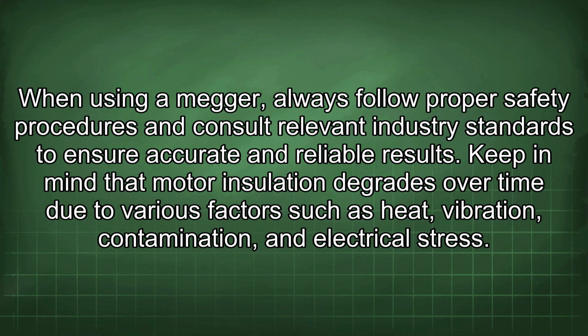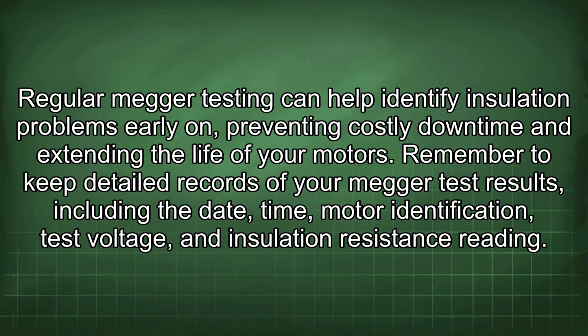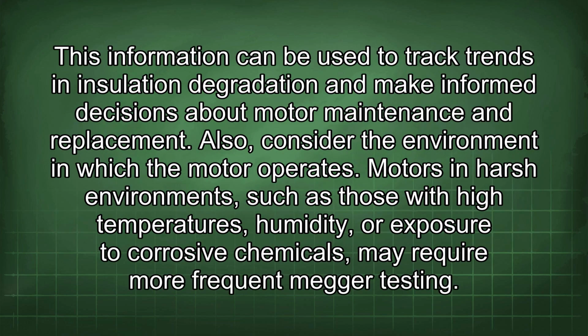Keep in mind that motor insulation degrades over time due to various factors such as heat, vibration, contamination, and electrical stress. Regular Megger testing can help identify insulation problems early on, preventing costly downtime and extending the life of your motors. Remember to keep detailed records of your Megger test results, including the date, time, motor identification, test voltage, and insulation resistance reading.